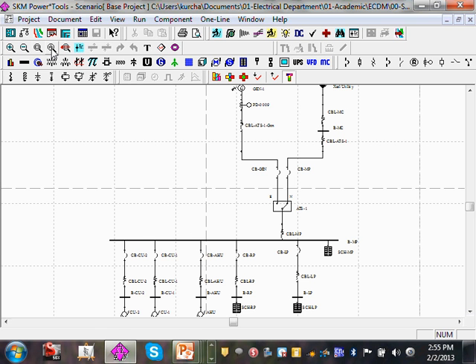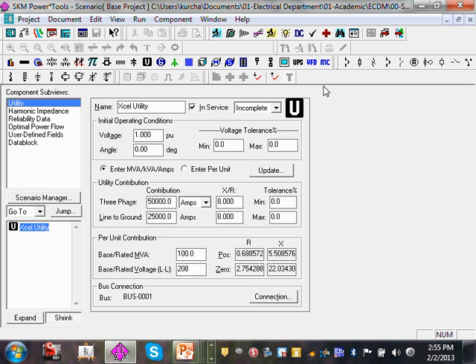So who cares? Let me just show you. When we click on one of these, here's what you get. This is the source of all evils, how much energy is going to push through your system. And this one happened to be, for our example, 50,000 amps at this location. So these 2 numbers, typically we get them from the utilities. That's the available short circuit. What does that mean? Meaning, if you take phase A to phase B to phase C, right at the secondary terminal of the Xcel transformer, right at this location, downtown Minneapolis, for example, and you flip the switch, that's how much the distribution system of Xcel is going to push right through your building.